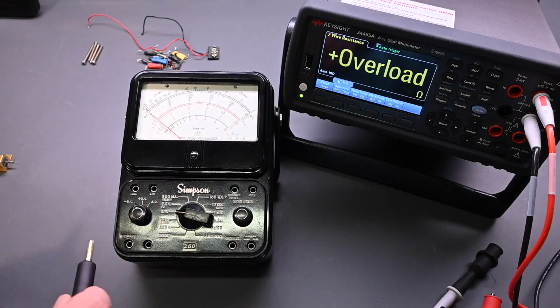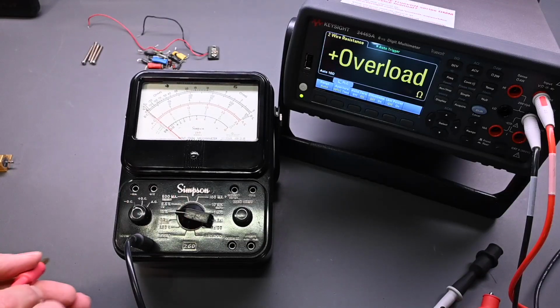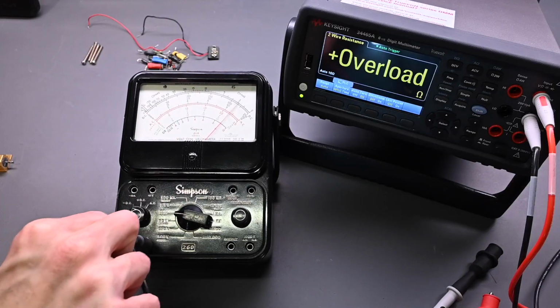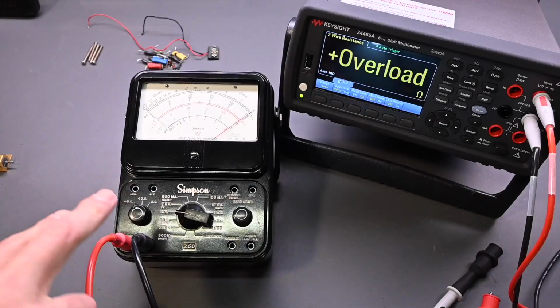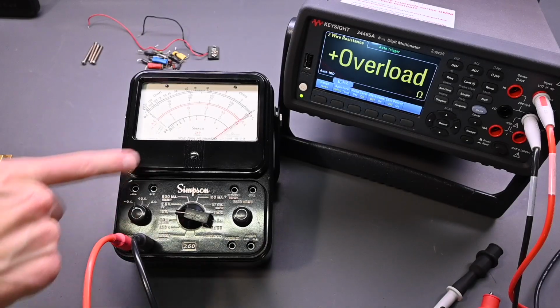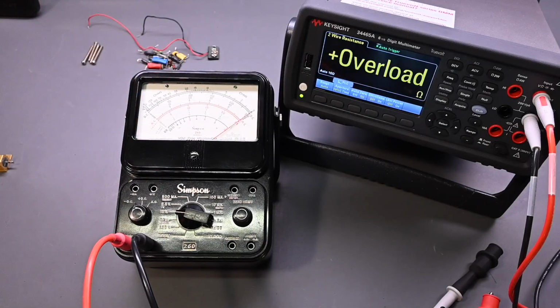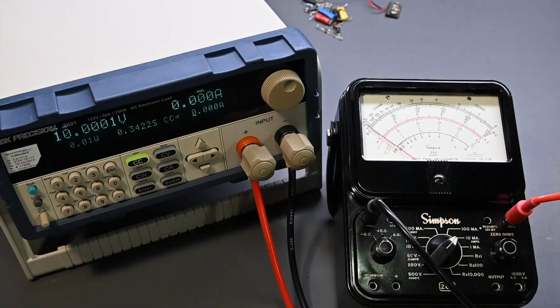But now we're going to reverse this. So negative that, common is positive, and yes, perfect. So you reverse the polarity, but this is on minus DC, and it works correctly. So perfect. Let's move on to the AC voltage calibration. I almost forgot about checking the 10 amp range on the Simpson 260 before I move on to calibrating its AC voltage ranges. So let's check that high current range now.